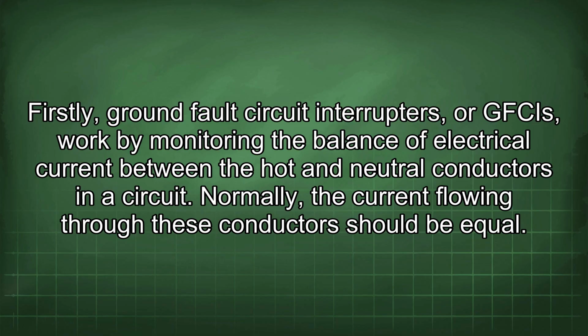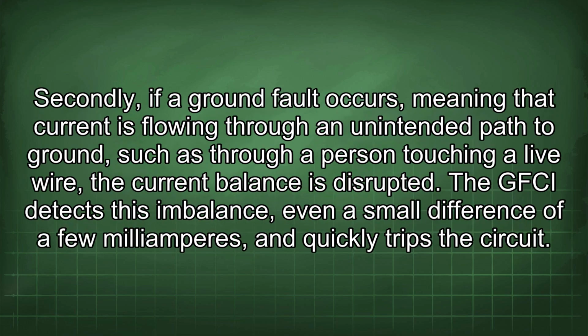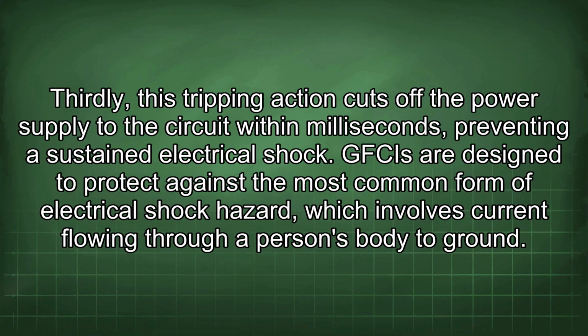Firstly, GFCIs work by monitoring the balance of electrical current between the hot and neutral conductors in the circuit. Normally, the current flowing through these conductors should be equal. Secondly, if a ground fault occurs, meaning the current is flowing through an unintended path to ground, such as through a person touching a live wire, the current balance is disrupted. The GFCI detects this imbalance, even a small difference of a few milliamperes, and quickly trips the circuit. Thirdly, this tripping action cuts off the power supply to the circuit within milliseconds, preventing a sustained electrical shock.